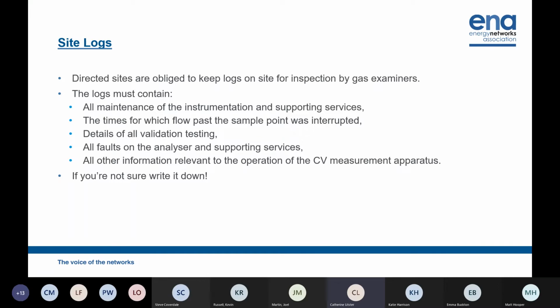In the letter of approval, the directed sites are obligated to keep logs on site for inspection by the gas examiner. These must contain all maintenance that is carried out on the flow rate average system, so instrumentation, support devices, the chromatographs, the software on site, all the equipment for that. Any time the flow stops past the sample point, so if you switch off your chromatograph for maintenance or there's a fault on it and you're not using any gas in the sample stream, this must be written down at the exact time it stopped and when it started again.